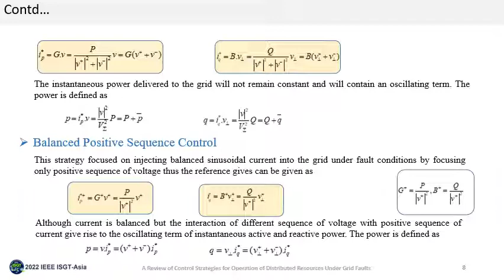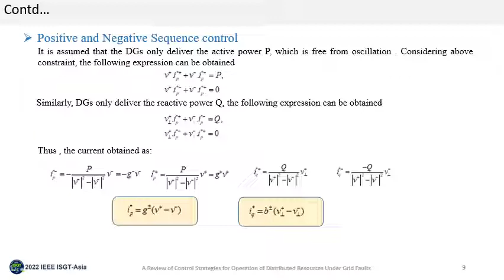But in the system, the voltage will have both positive and negative components. So the interaction of the negative component of voltage with the positive component of the current will give rise again to oscillation. So in this strategy, the oscillating term in both the active and reactive power cannot be removed. Now the last strategy is the positive and negative sequence control. In this strategy, the active power which is generated is free from oscillation when we are operating at unity power factor. Both the positive and negative sequence components are taken, and the current which is generated consists of both positive and negative sequence components.